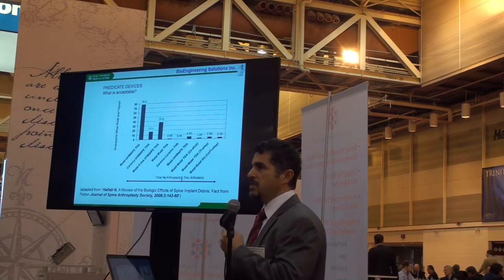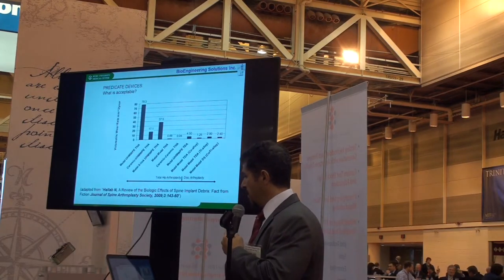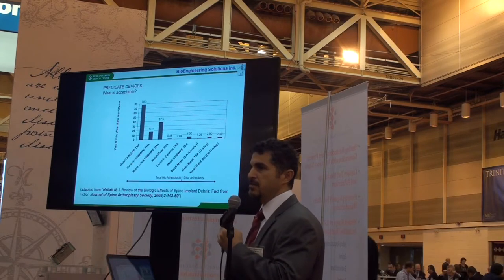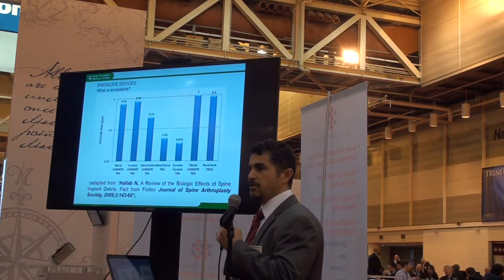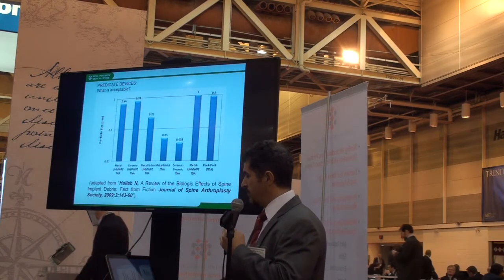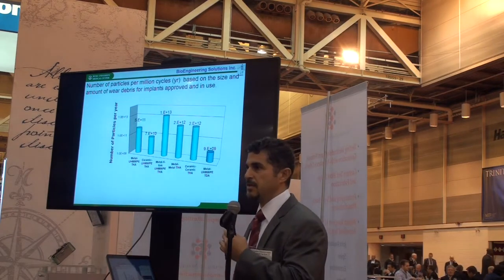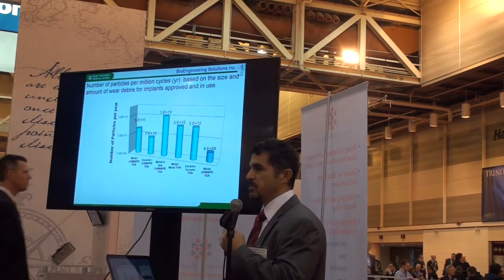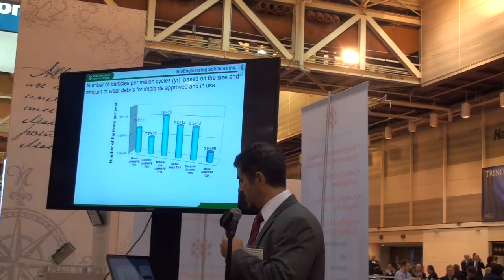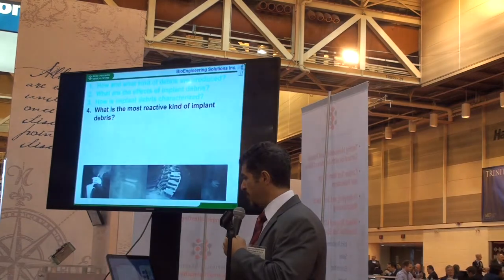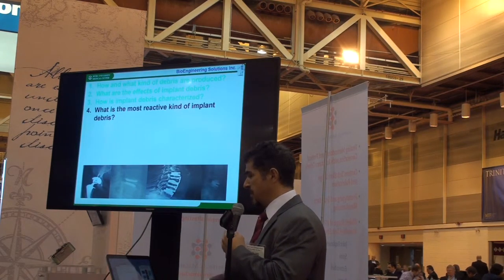What do you do with this information? You relate it back to predicate devices — how much total wear is produced, what are the particle sizes — and from that you get measures of total numbers of particles being disseminated that could possibly cause a reaction. This allows nice comparison to other implants that are out there.